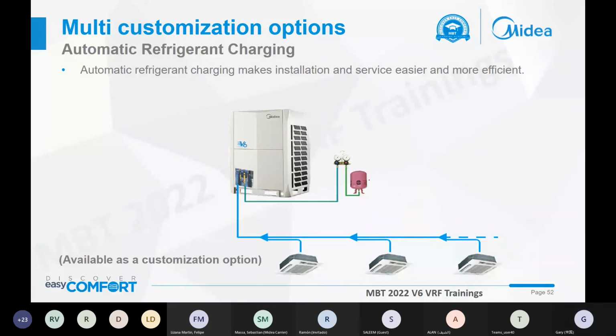The other function is the automatic refrigerant charge. As you know, our VRF is always for big projects with so many indoor units. So the default refrigerant charge is normally not enough, and in most cases we need an additional recharge when we install or commission. Normally we calculate how much refrigerant to charge by hand, but this way is not very correct and not very precise.